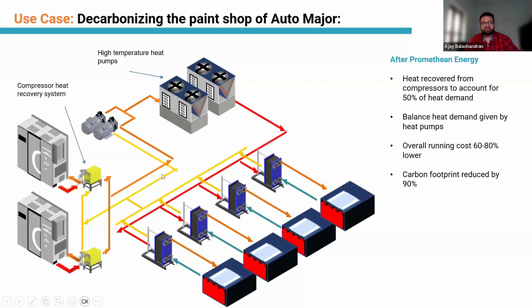Also, the running cost dropped - they used to spend 65 lakhs on fuel oil, now hardly anything, because of these heat recovery systems and heat pumps. About 50% of the total heat is balanced by the air compressors, and only when there's a requirement for more heat do the heat pumps work. Across all other times, only the air compressor heat recovery is used by the paint shop.